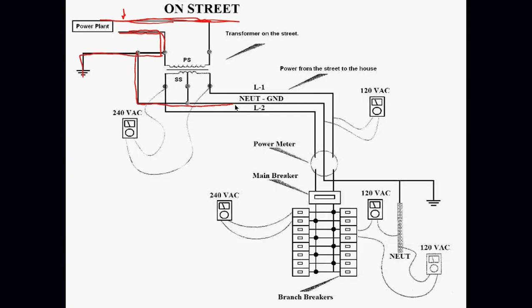It also comes off the center tap of the transformer. That's why this is not necessarily, I can't call it a dead leg, but it is the center of everything. Okay, it's grounded at the house. It's grounded in the power company's world. It's the center tap of the transformer. Okay? Neutral is important. This transformer on the street, the primary side, 13,000 volts.